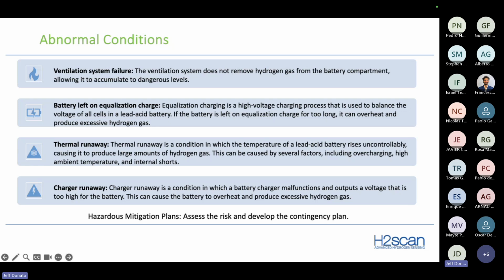So they want to know, what is the mitigation plan if we have a mechanical failure? And then also, is the mitigation system or the gas purge system moving enough air for other types of events, best case and worst case scenarios? And I'm going to show you an example here in another slide.